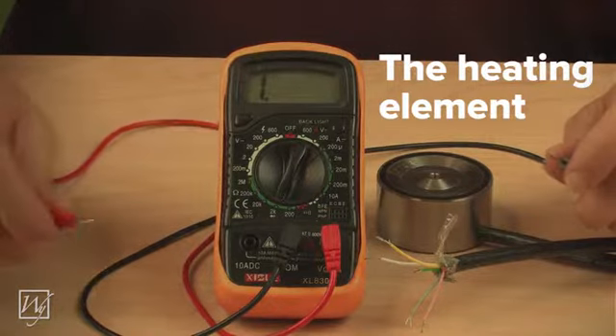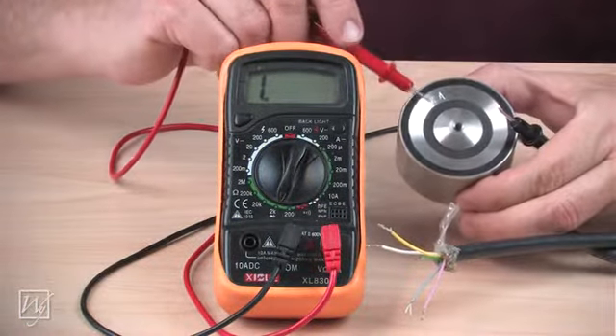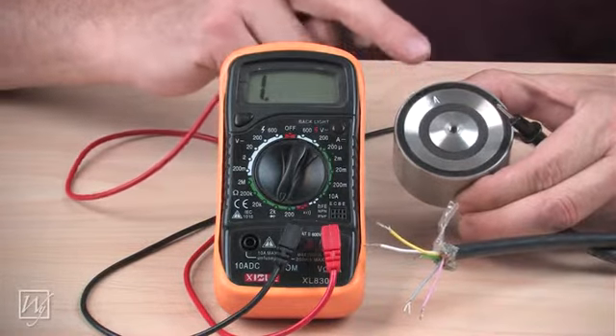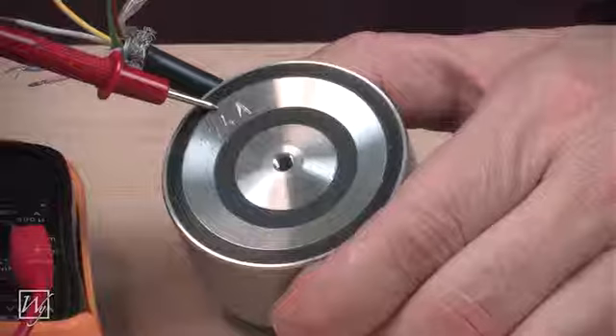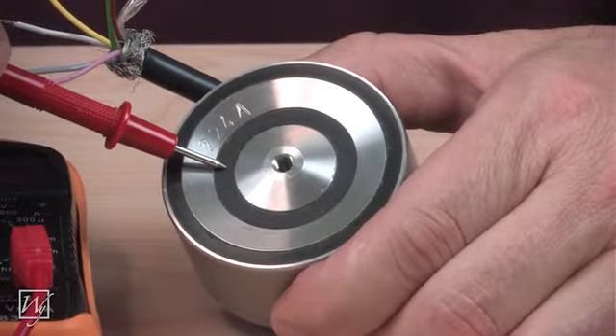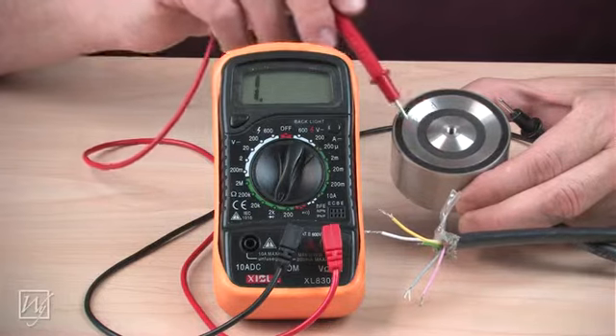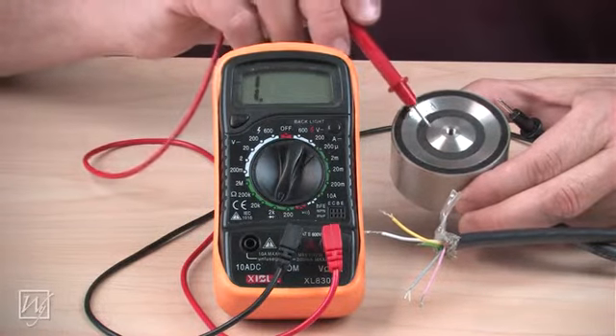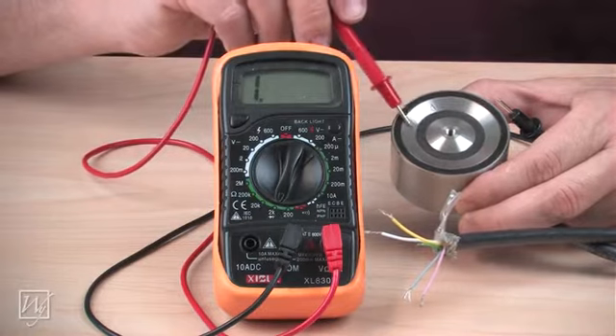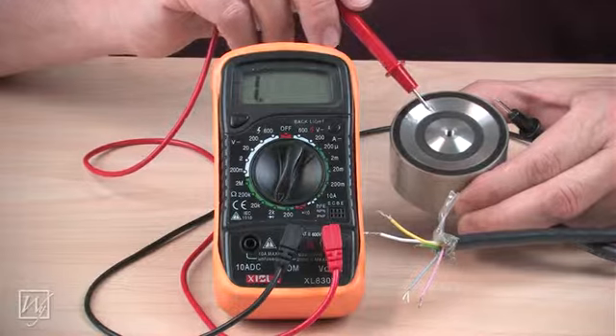The first section we're going to talk about is the heating element. This unit has a heating element built into it and the reason is when snow is falling and it hits the sensor, that snow has to be melted to make a complete circuit between the middle ring and the center ring. So if this were not heating, it would never melt the snow, it would never bridge this gap, and it would never turn the sensor on to tell it that it was indeed wet.